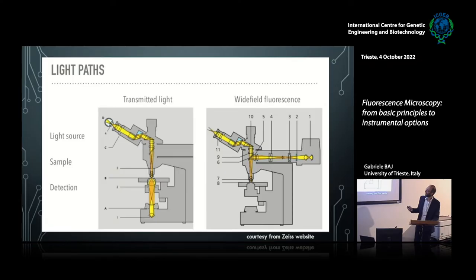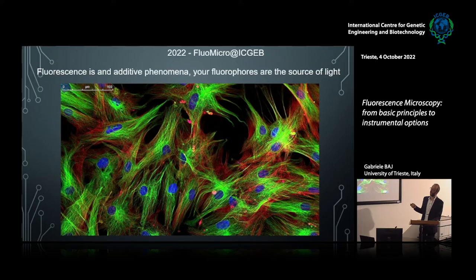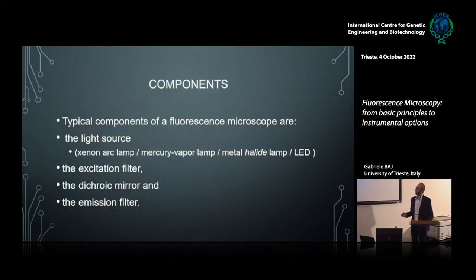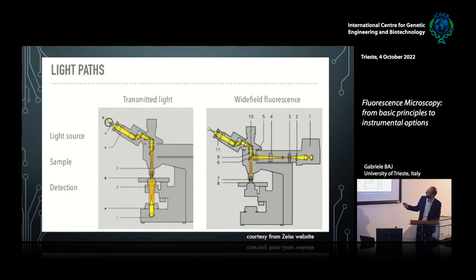There is one particular element in the middle that changes the behavior of the microscope from a regular bright-field microscope to a fluorescent microscope. Fluorescence is an additive phenomenon because you keep collecting photons from your sample at different wavelengths and can produce different multicolor images. The typical components of an epifluorescence microscope are a particular light source, an excitation filter, a dichroic mirror, and an emission filter.